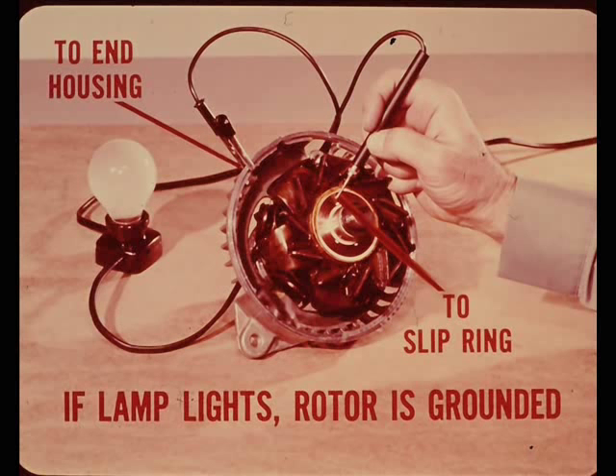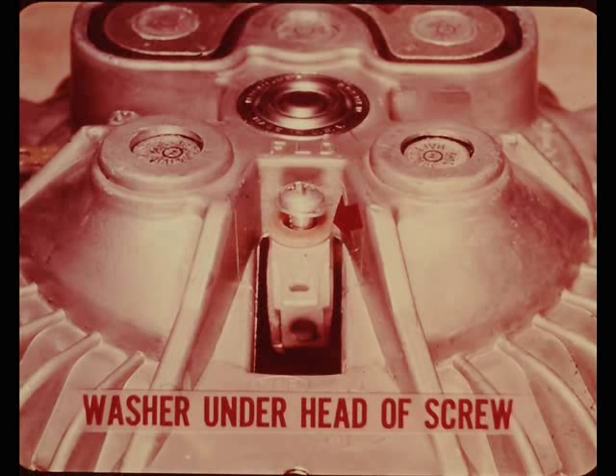To locate the ground, first remove the brush holders and the end housing. Then, clip one test lead to the remaining end housing and touch the test prod to either slip ring. If the lamp still lights, it means that the brushes are okay, but the rotor is grounded. Make sure a nylon washer is under the head of each brush holder attaching screw, or you'll get a direct ground to the end housing. This is a special size screw, so don't try any substitutes.